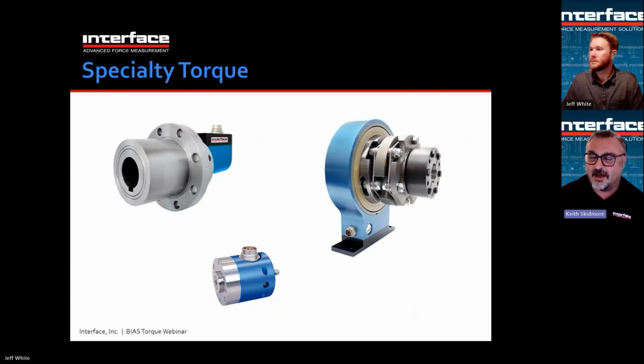On the right is an actual coupling torque sensor where the coupling is integrated into the torque measurement. So part of the coupling is actually manufactured as the torque sensor and the strain gauges are applied. And this would be a bearingless type torque sensor with the induction ring around the rotating assembly. And then on the bottom is a very, very small capacity torque sensor.